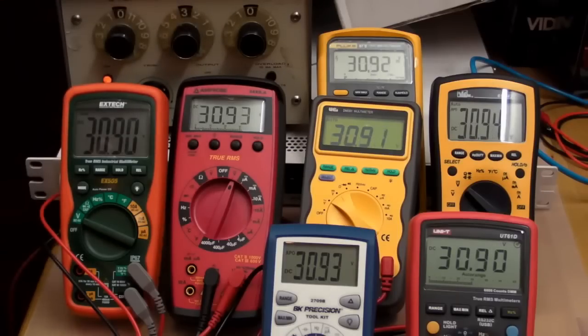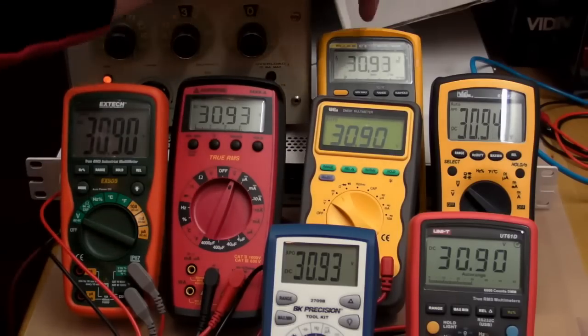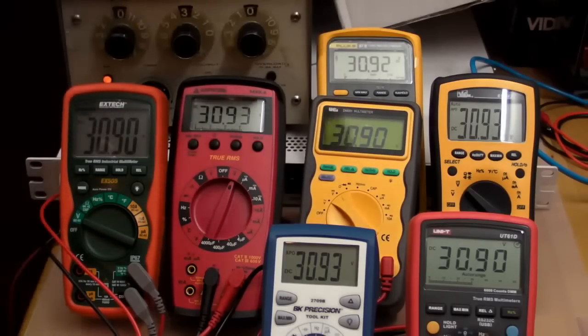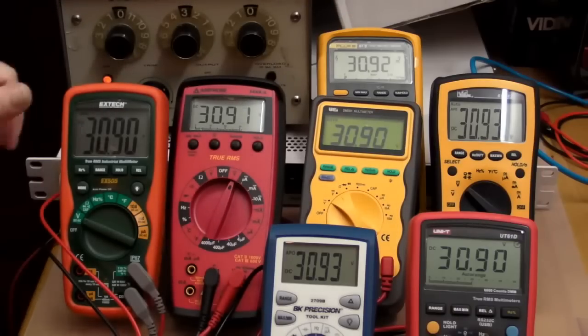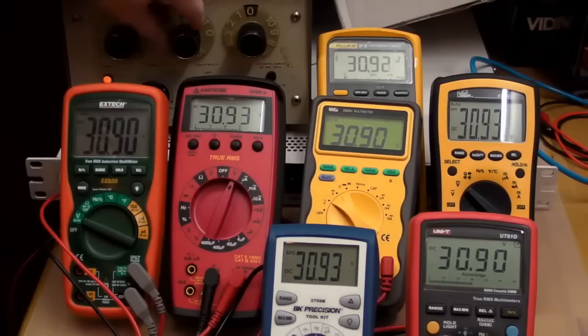Let's ramp it down to test the 40 volt range. We've got 30.93 on the Fluke, and all the others are pretty darn close, well within spec.